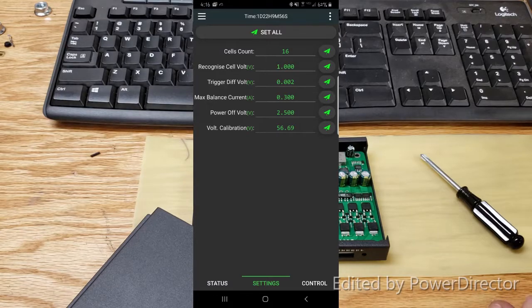And a voltage calibration at 56.69 volts for my whole pack, which divides into 3.544 volts per module. Those are the settings. Control doesn't do anything, the device doesn't have it. On the status screen you can turn balancing on and off and see your module or cell voltages. That's all there is to it.